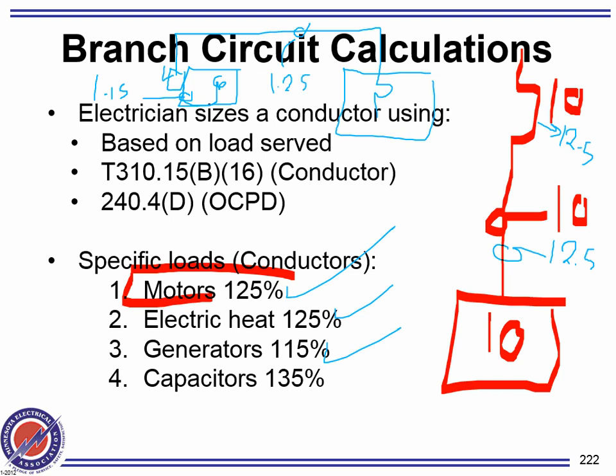That's a factory wiring side. Well, sometimes we also put the generator in a bigger building, put the generator here, and we put the breaker on a wall. Then you are allowed to go 1.15. Capacitors. Now capacitors are a nasty, ugly creature.